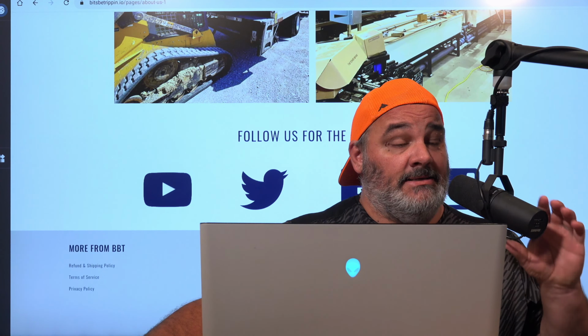Our current site has 480, 277, and it's directly connected. We have just a service shutdown and no switchgear. We're going right from there with no switchgear. And because we're on the substation, it's essentially a cabinet that's giving us single phase 277 for the miners, which required us to have specific power supplies that could handle 277. But if we were going to do our first original plan where we were taking 480 to 415, 240, we would have had step down transformers.